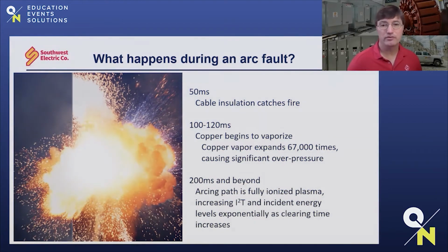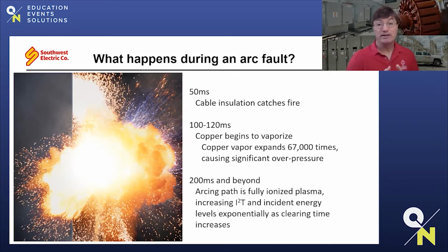During an arc fault, you may have seen some videos and explosions. What's actually happening is that this current is flowing through air instead of through a conductor, and instead of being controlled and directed properly, the amount of current involved increases dramatically. Because of this high current, within 50 milliseconds, the intense heat that generates actually catches the cable insulation on fire, which in itself is intended to be fire resistant. But because of the heat, it's just overwhelming.